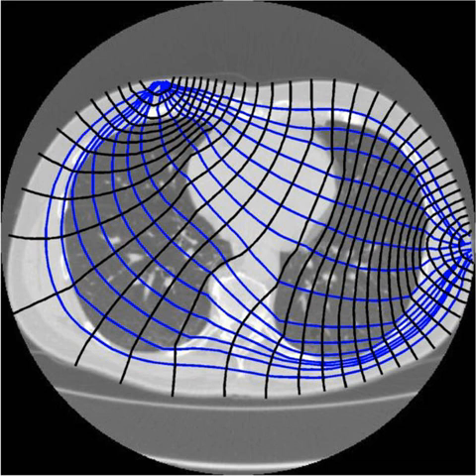Earlier EIT systems still used an analog demodulation circuit to convert the alternating voltage to a direct current level before running it through an analog to digital converter. Newer systems convert the alternating signal directly before performing digital demodulation. Depending on indication, some EIT systems are capable of working at multiple frequencies and measuring both magnitude and phase of the voltage. Voltages measured are passed on to a computer to perform image reconstruction and display. The choice of current patterns affects the signal-to-noise ratio significantly.